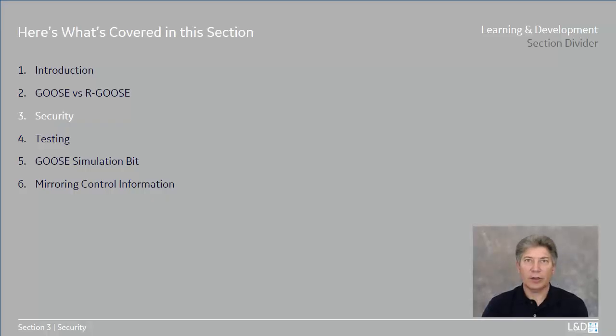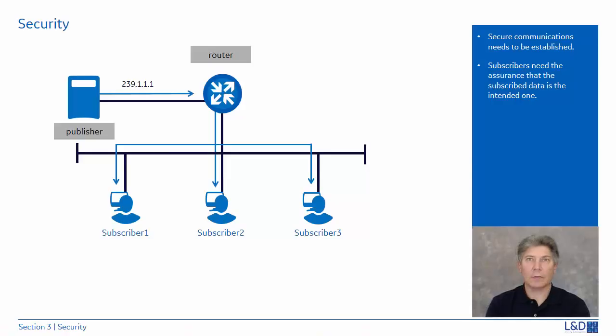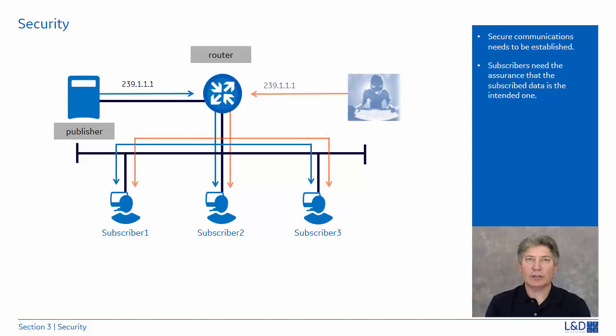In this section, we'll take a look at how the routable GOOSE is kept secure. In a secure network, the publisher is streaming multicast data onto the network. The subscribers are monitoring and listening for the data. Everything appears to be secure. What happens if we have a security breach? The intruder could, in effect, publish incorrect or damaging data. The subscribers would not know any better. The subscribed data appears to be coming from the appropriate source.